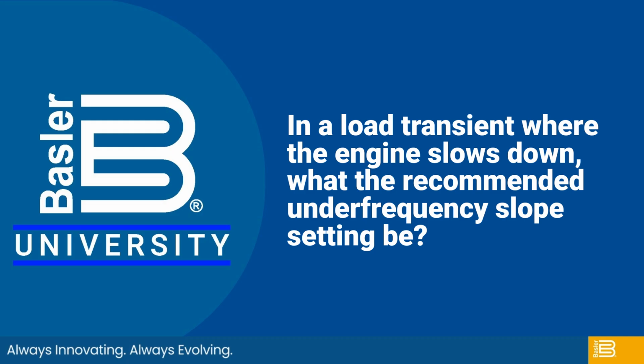Usually with the slope, some machines actually run at idle speeds. If you need your generator to not be producing voltage while you're at your idle speed, then you would set your slope such that it would reduce the generator voltage as low as possible at that idle speed. And that idle speed on a 60 hertz machine might be somewhere around 45 hertz. So there is a way you can calculate what your slope would need to be in order to reduce generator voltage to essentially zero. There will be some residual voltage on the machine. The DECS won't be able to drive voltage completely to zero.